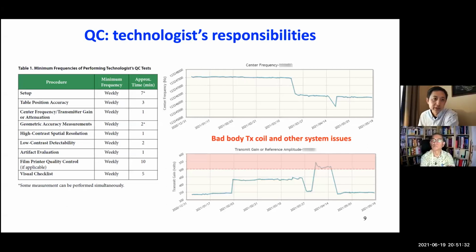They will just set up the phantom and scan. That will be done within 10 minutes. And then they push the image to a location. Then we have a system that will process everything automatically. Here, I just show you, this is a daily result of center frequency and transmitter gain. This is nothing but a recording from the data.